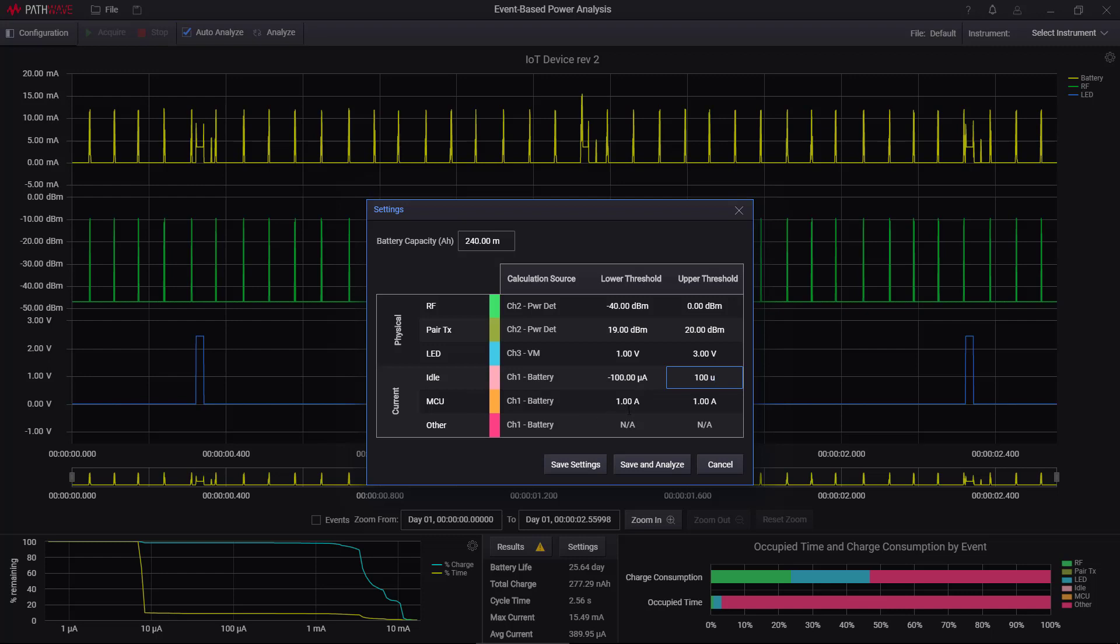And then if it gets above 100 microamps, but less than one amp, so from 100 microamps to one amp, I'm going to call that active.